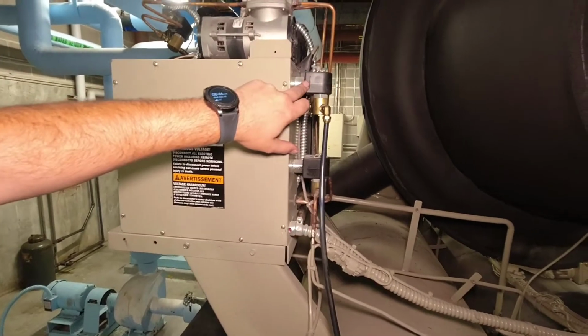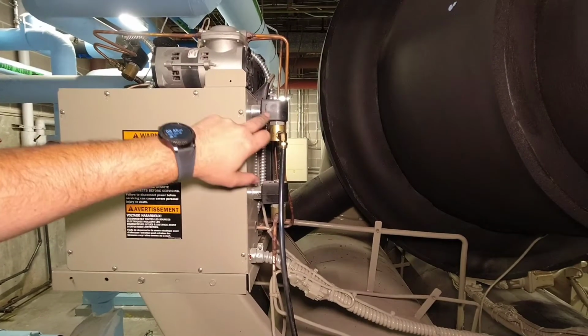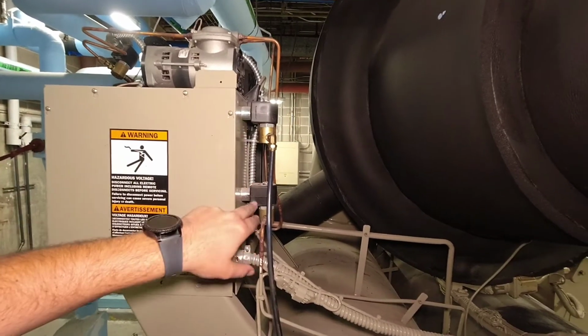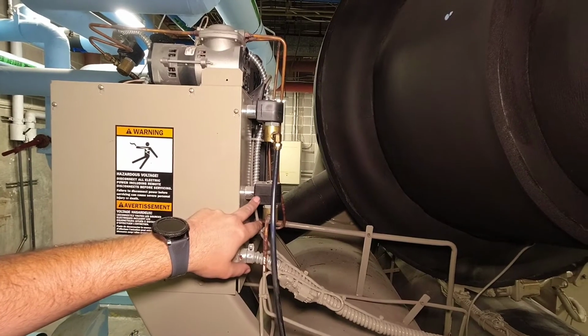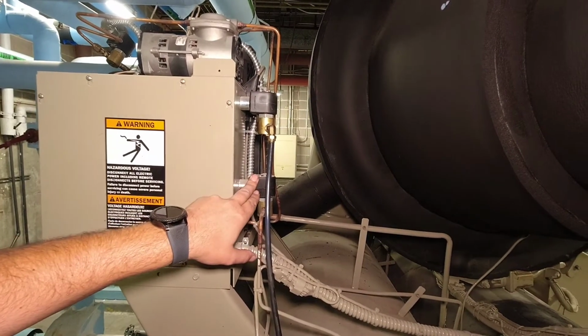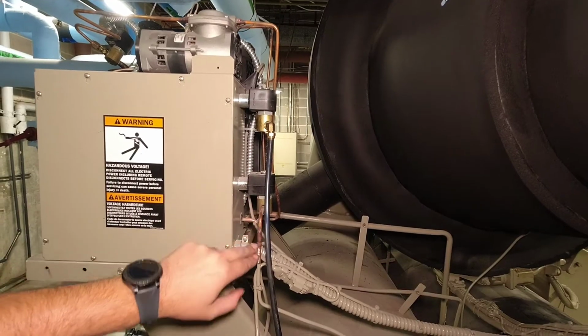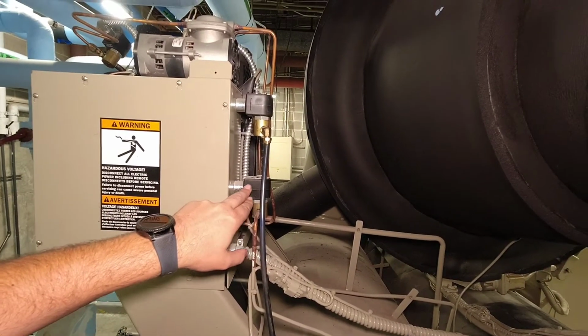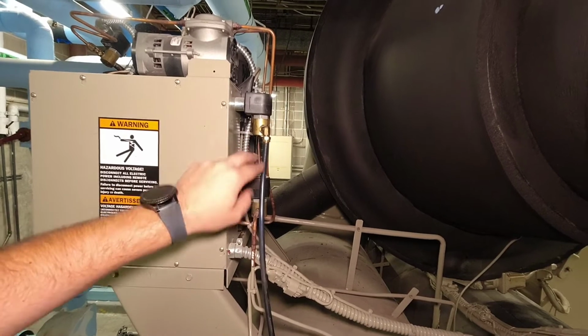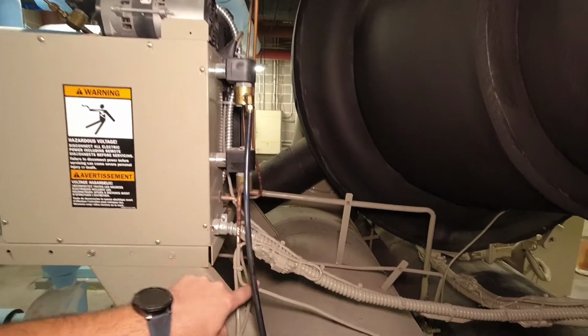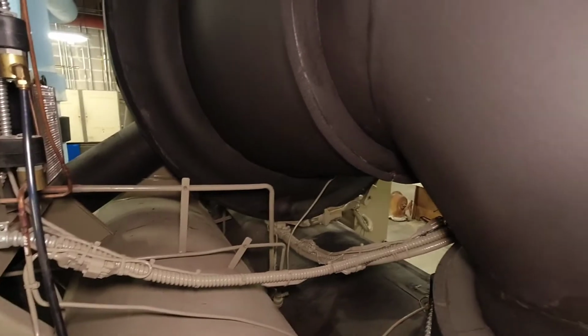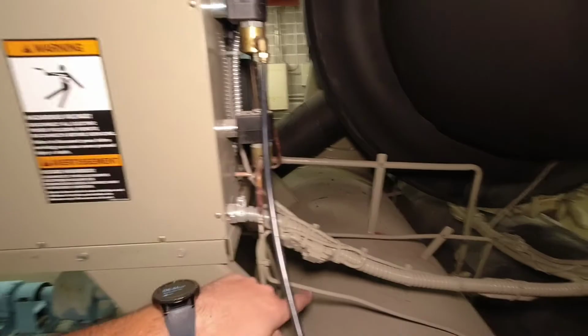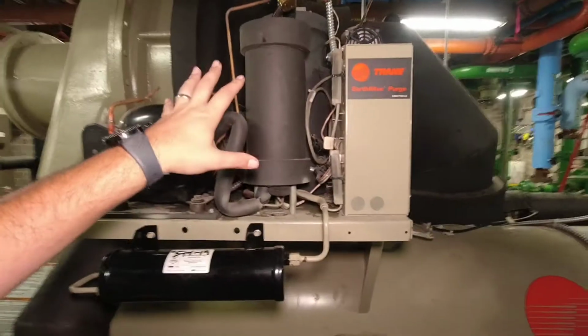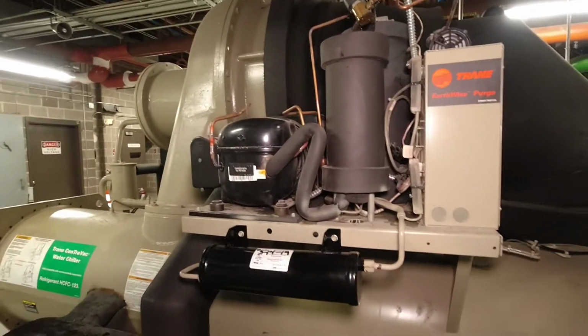And so on systems that don't have that, you'll only have one pump out solenoid over here. But on these particular systems that have that recovery ability, you'll have a second solenoid, and its specific task is for the reclaim cycle. Whenever that tank heats up, it allows that refrigerant to go back into the evaporator. As it heats up, that evaporator pulls that refrigerant. That's your purge unit. That's its basic function.